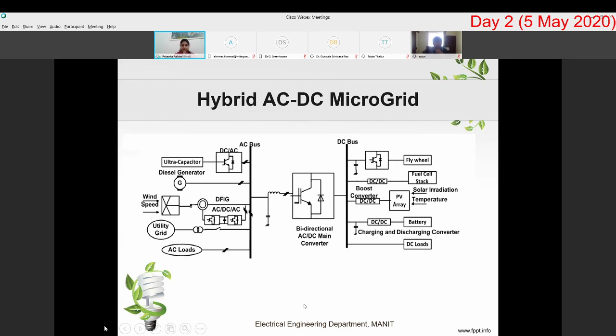In the previous figure, the DC microgrid just had the DC bus, and the AC microgrid just had the AC bus. Here you have both buses, the AC bus as well as the DC bus. If you have an AC source producing AC, it can be directly integrated to the AC bus, such as the DFIG. If you have a DC source, such as the battery or the PV source, it can be directly integrated to the DC bus. DC loads can be directly connected to the DC bus, and AC loads can be directly connected to the AC bus.